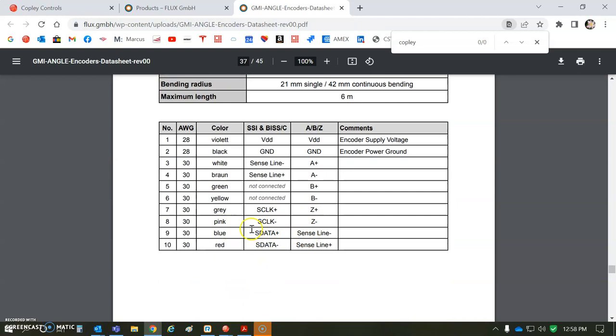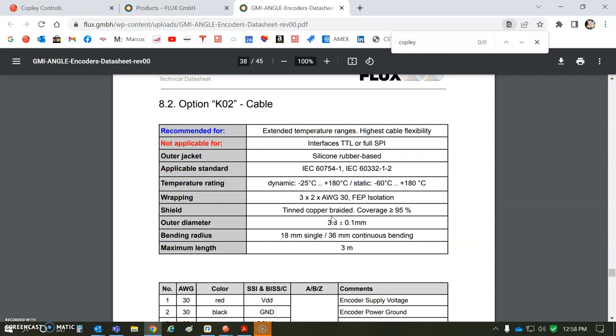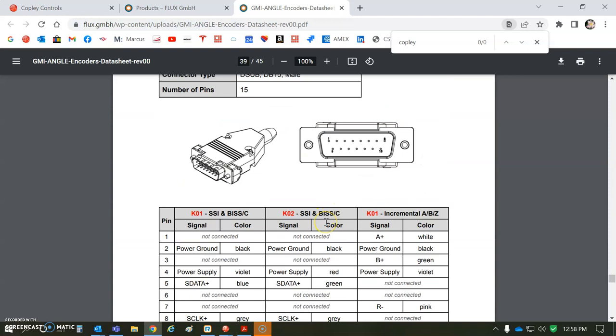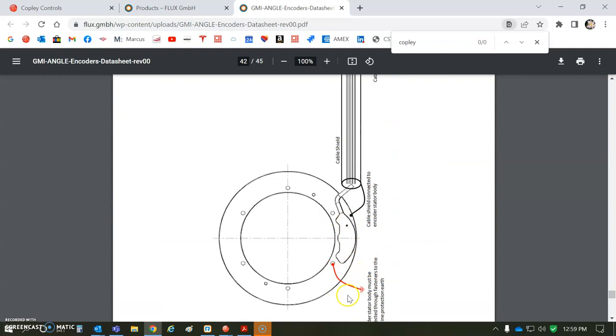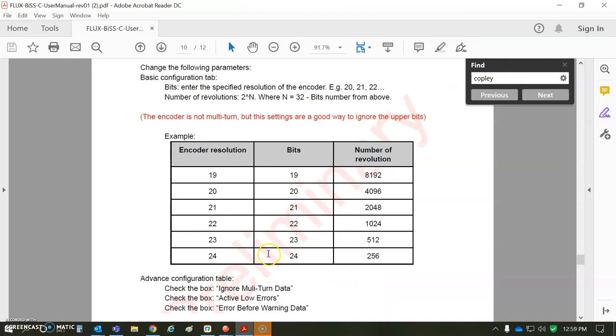Data minus is red, clock plus is gray, clock minus is pink, plus five is violet, ground is black. If you had a sense line for long distance, you might as well just double it up with a plus five of ground. If you want incremental, it's A-not, B, B-not, and index. That's an option—one or the other or both even. Here's the cable options, different cable types and the colors and the pinouts. Here's that shield again: motor case yes, but feedback shield no. They did a good job documenting this. It's not multi-turn, but they'll say it's 23 bits with a number of revs of 512, so that's nine bits. That adds up to 32.